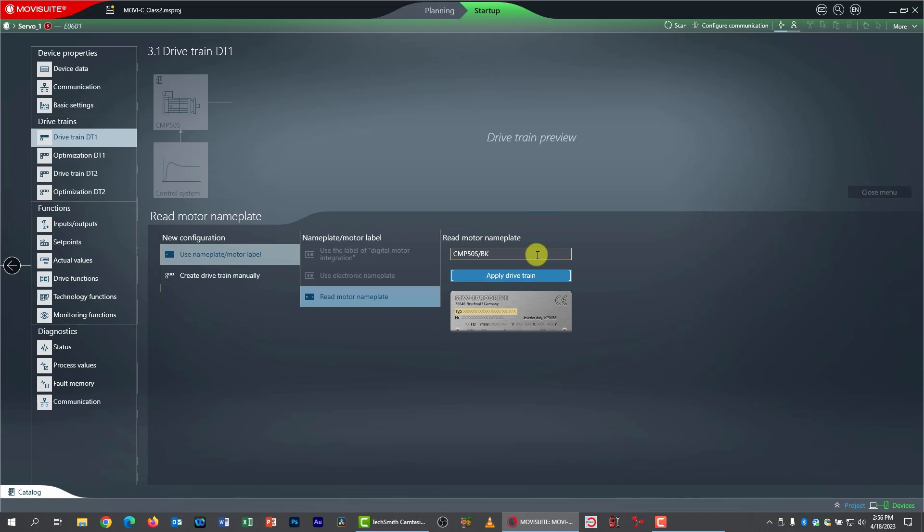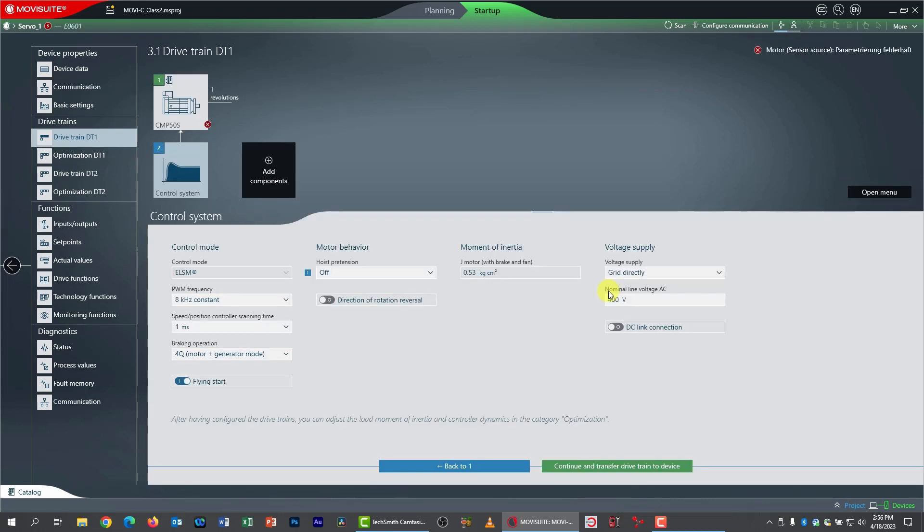and type in the nomenclature, which is CMP50S slash BK. So that's the servo nomenclature and the brake. I got that from the physical nameplate on the motor. I'll click apply drivetrain. And that's that.